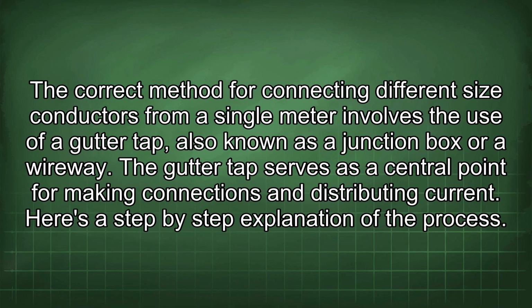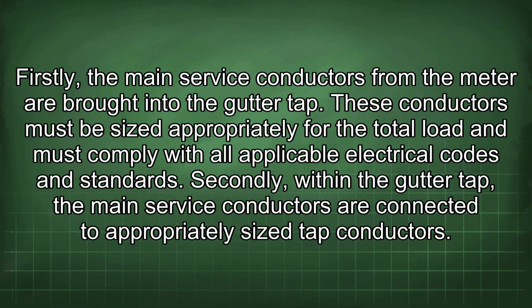The correct method for connecting different size conductors from a single meter involves the use of a gutter tap, also known as a junction box or a wireway. The gutter tap serves as a central point for making connections and distributing current. Here's a step-by-step explanation of the process. Firstly, the main service conductors from the meter are brought into the gutter tap. These conductors must be sized appropriately for the total load and must comply with all applicable electrical codes and standards.